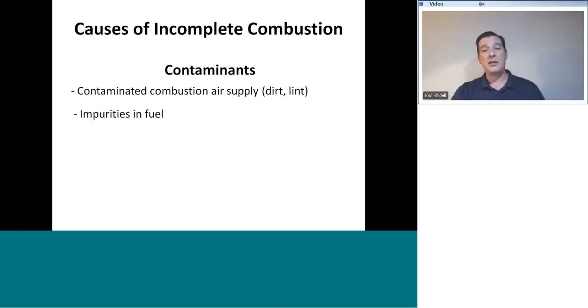Contaminants such as dirty fuel, dirty combustion air supply, this is especially important in propane markets to realize. Sometimes your propane provider might start getting their fuel from another source, and we have some issues, I know, in certain parts of eastern Colorado where high-efficiency boilers were working fine for a number of years, and then all of a sudden they sooted up and they wouldn't run correctly anymore because something changed in the fuel gas delivery system. We started getting some impurities in the fuel, and it caused those burners to operate incorrectly.